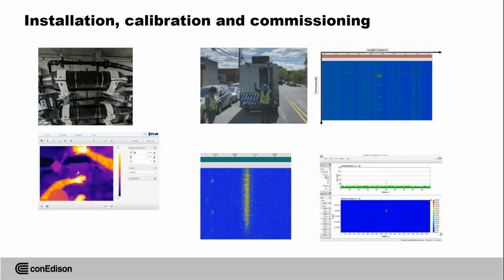So what you see on the left side, this is the view from the camera, from the system, view from camera on the joints. You see joint supports. And picture below, left bottom picture, this is camera turned into infrared. Same view, infrared. You see hands of the splicers, which basically shows this is the temperature of the human body, around 36 degrees C. And you can see the much cooler temperature of the joint here. And this is what we did during calibration. That's why you don't see any heat from the cable. It's not energized yet, but we calibrate the cameras.